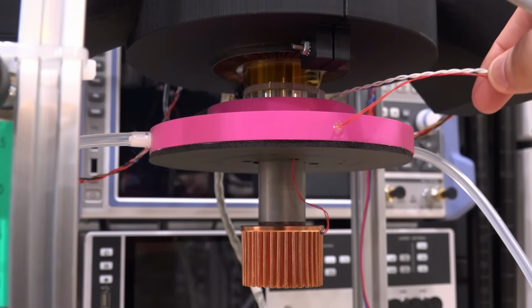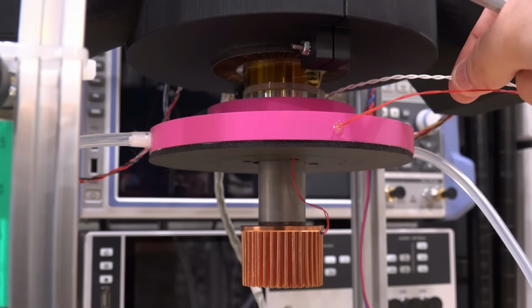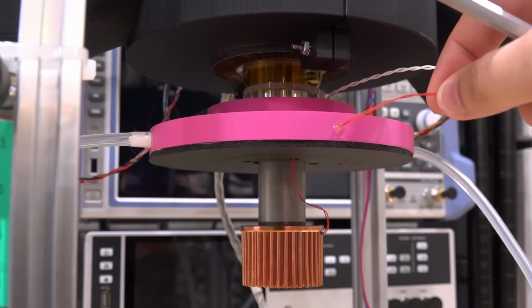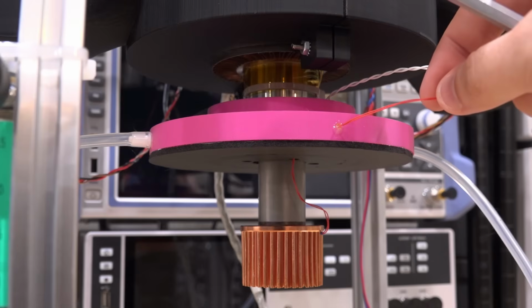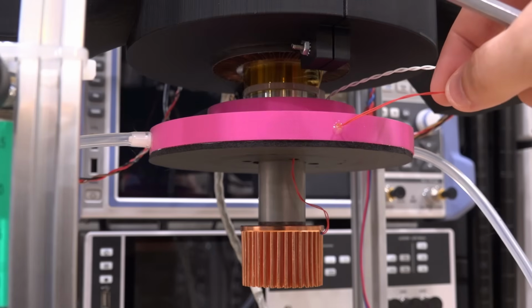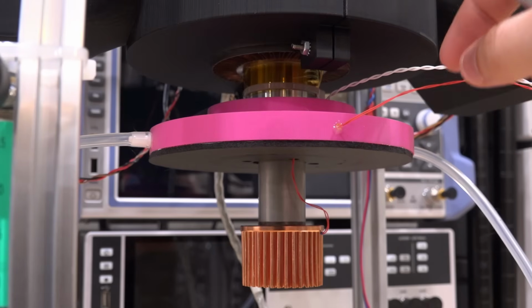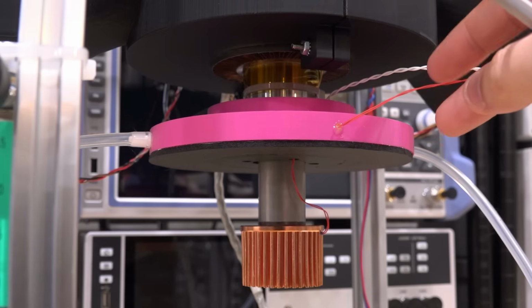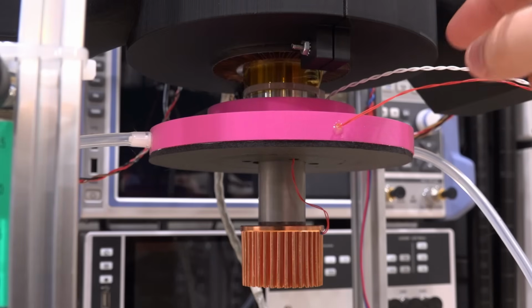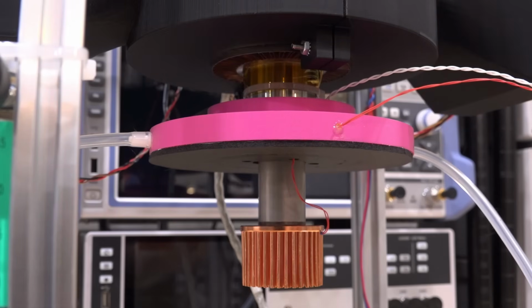These 2 temperature sensors are quite different from each other. This is a thermistor, an NTC thermistor. This one is actually a PN junction, and the unit inside the vacuum chamber of the superconducting filter is a tiny surface mount wire bonded component. Now we can't really use that because it's really fragile, so I had to find a replacement diode. I'll talk about why that PN junction actually works.